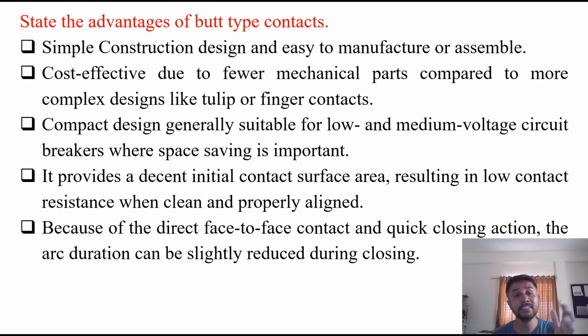It has a simple construction design and is easy to manufacture or assemble. It is cost effective due to fewer mechanical parts compared to more complex designs like tulip or finger type contacts. Compact design, generally suitable for low and medium voltage circuit breakers where space saving is important. It provides a decent initial contact surface area, resulting in low contact resistance when clean and properly aligned. Because of the direct face-to-face contact and quick closing action, the arc duration can be slightly reduced during closing. So these are some advantages of butt type contacts of circuit breaker.